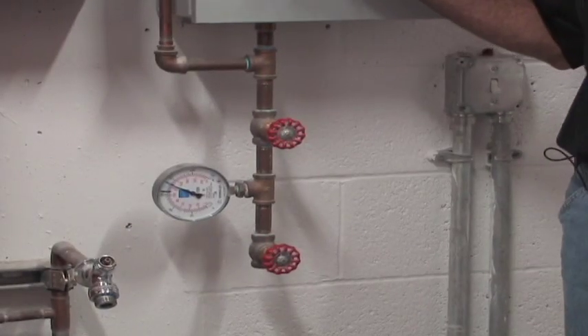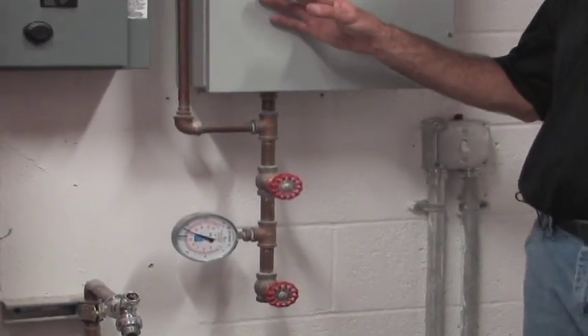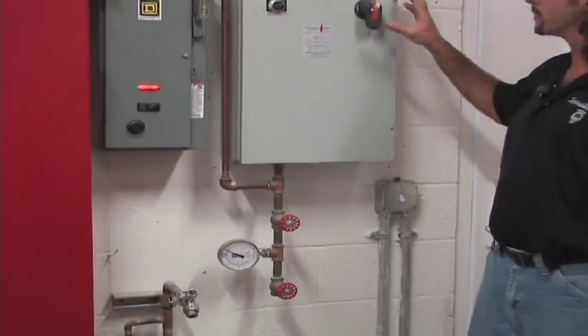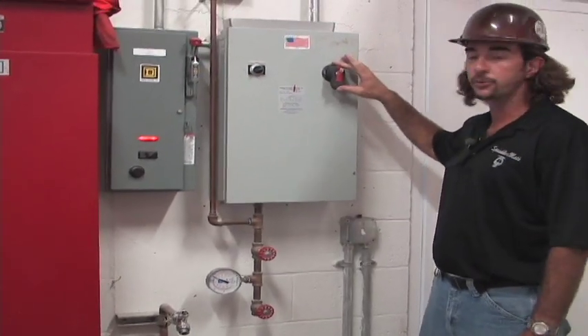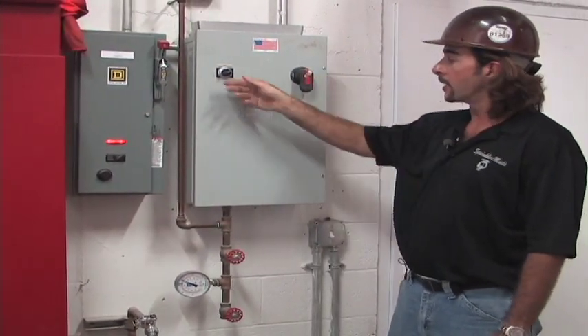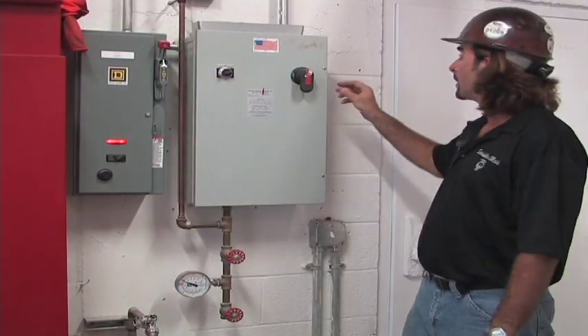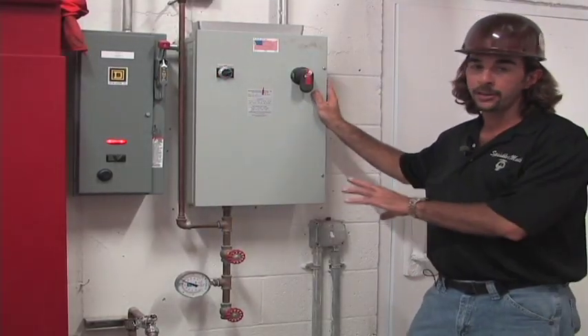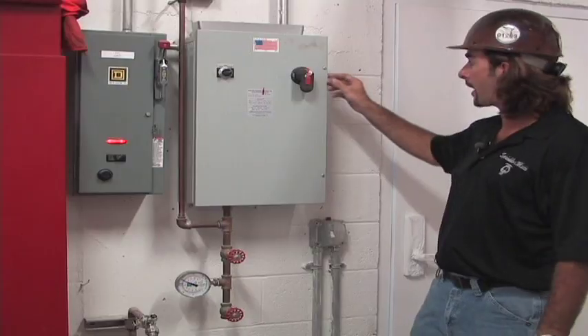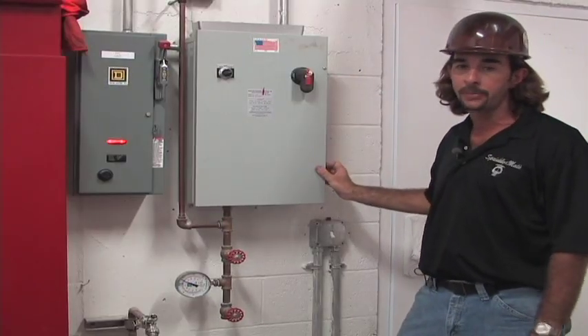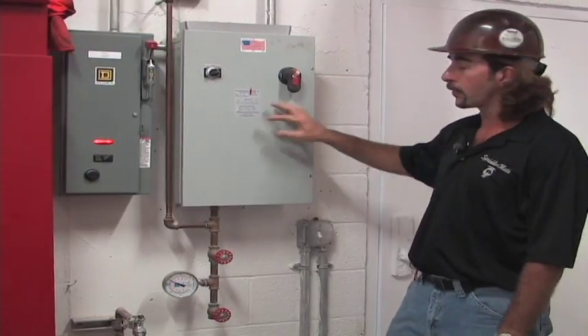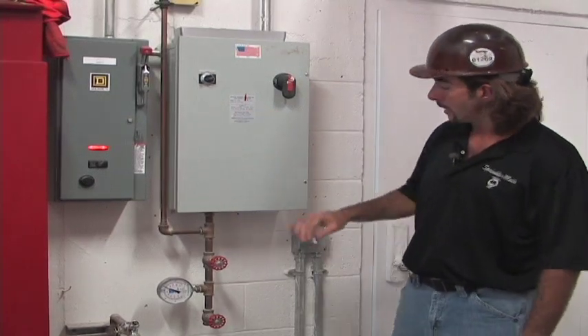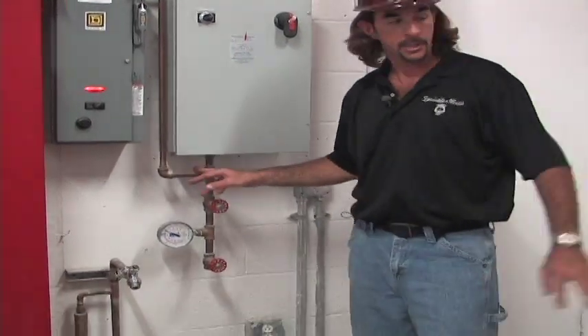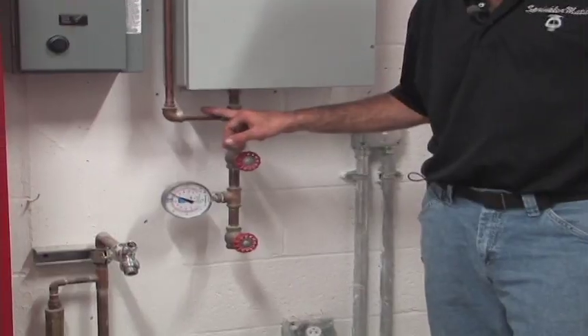We're going to run through the basic operation of the jockey pump. Like I said, our normal position is going to be our switch on and our selector switch in auto. This is a 480 volt panel along with the jockey pump, so any access behind this door needs to be done by a certified electrician, 480 volts. We have our sensor line coming from the discharge side piping of our jockey pump.